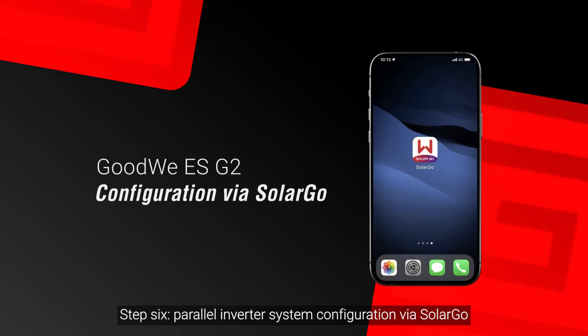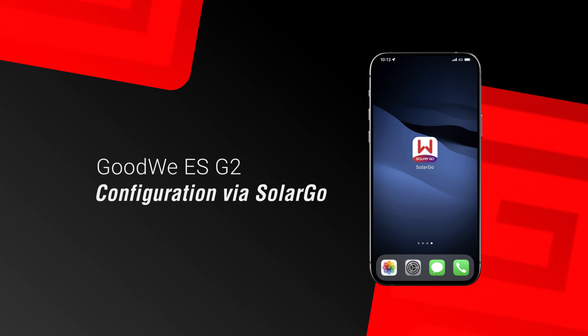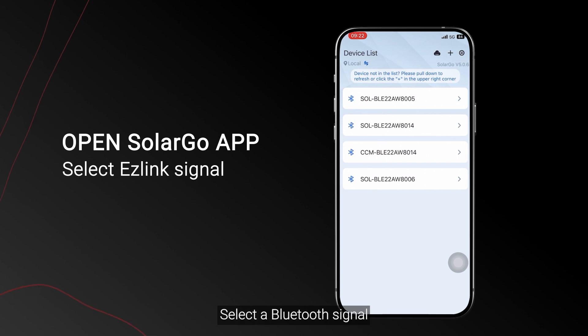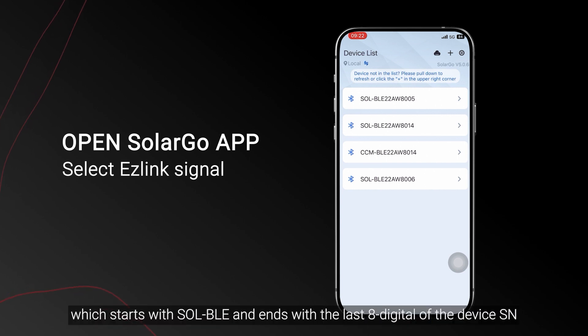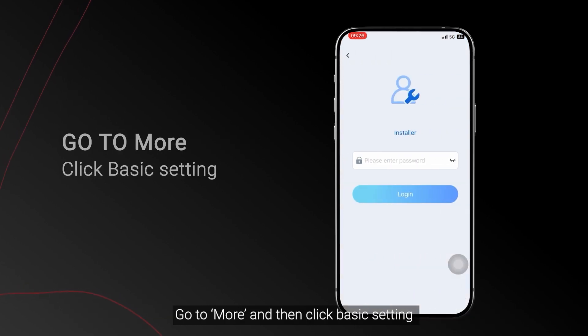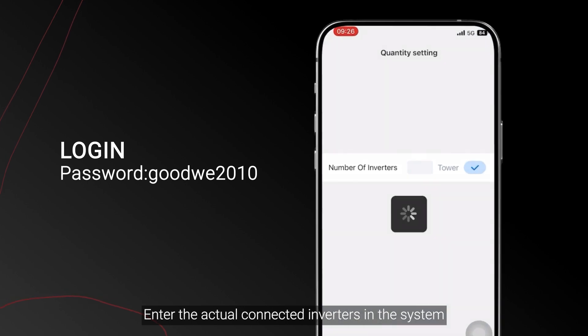Step 6: Parallel inverter system configuration via SolarGo. Enter SolarGo and make sure you switch to local mode. Select a Bluetooth signal which starts with SOL-BLE and ends with the last eight digits of the device SN. Go to More and then click Basic Setting. Enter the actual number of connected inverters in the system.